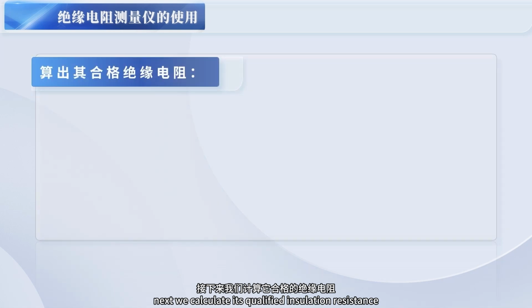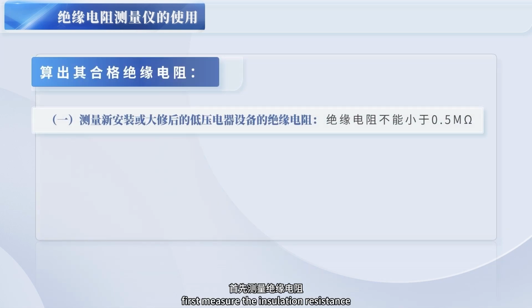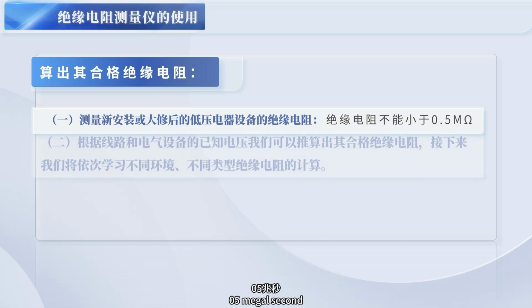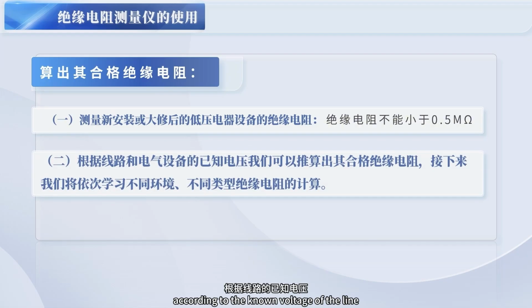We know the voltage of the motor cable. Next we calculate its qualified insulation resistance. First, measure the insulation resistance. After electrical equipment is newly installed or repaired, the insulation resistance must not be less than 0.5 megohms. According to the known voltage of the line and electrical equipment, we can calculate its qualified insulation resistance.